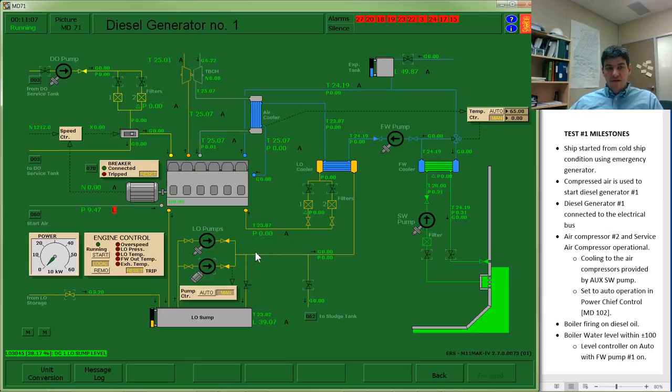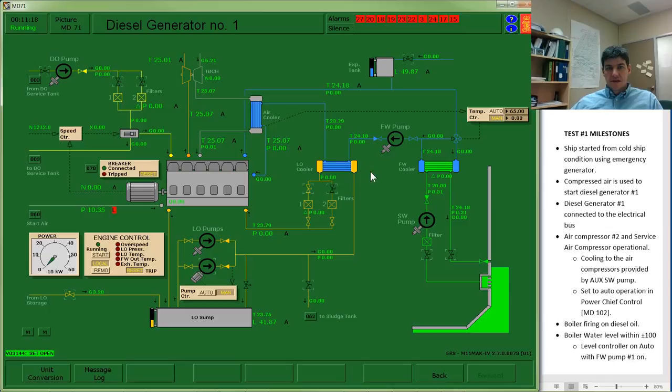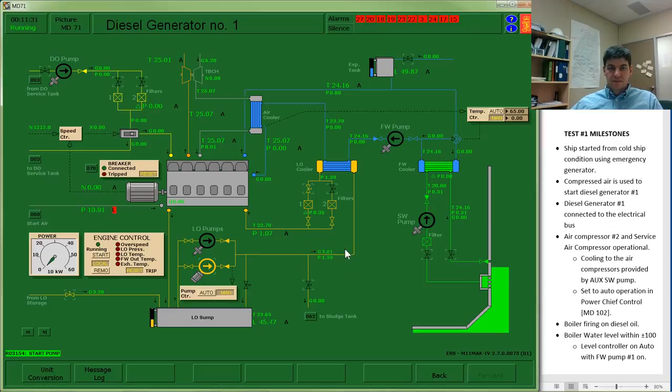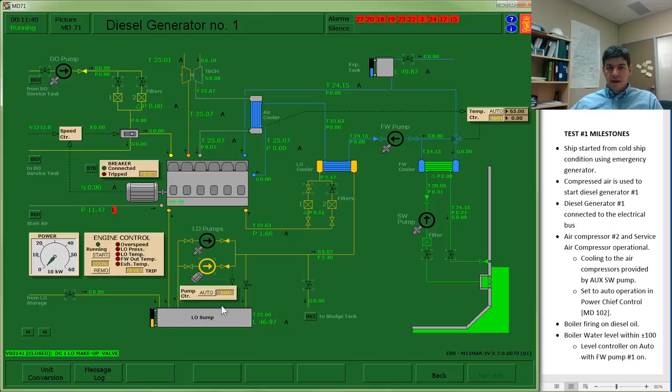The pathway for oil, what I want to do is I want oil to be circulating into this engine before I turn it on. So I'll need to open up a valve through one of the filters. And then I will be using the manual control on the lube oil pump. When I turn it on, you can see my flow is increasing and my pressure is increasing. If I'm okay with where my level is, then I'm okay to turn off my makeup valve and I will stop filling up the tank.